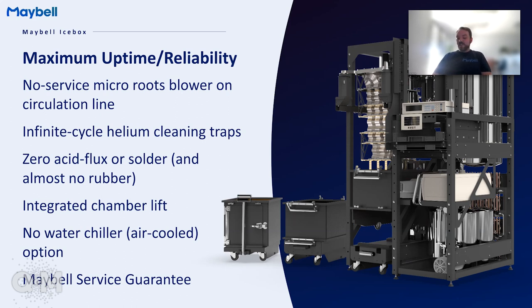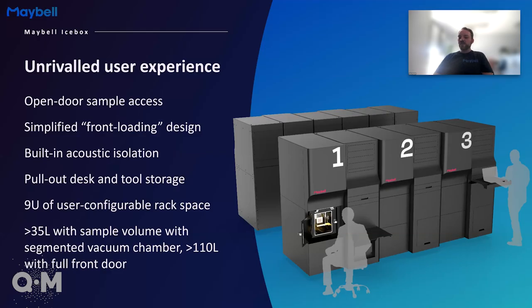Finally, I think all of us have experienced a flooded lab at some point. We can run this system either water chilled, if you have a water chiller that you're happy with, or central water, or air cooled. You pair that with the usability improvements that we've made to the system: acoustic isolation so that the pulse tube isn't so loud, the front door, the desk, the front loading design so that you can connectorize everything from 3 Kelvin all the way to the sample chamber outside the fridge on the table at eye level, and then insert the entire thing at once. And all you have to do is fasten down a couple bolts, and it makes for a very different and significantly streamlined way of interacting with your system.